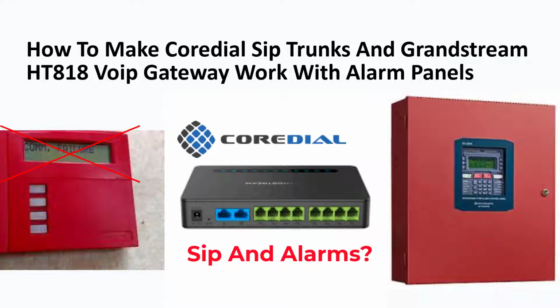However, with POTS lines being faded out these days, you want to have a dependable VoIP product that can communicate with a fire panel consistently, or you're going to need to pay the expensive cellular protocol cost to communicate with your panel. And after years of frustration trying to use VoIP lines with fire panels, I finally tweaked the Grandstream HT818 to communicate with the fire panels, enabling the completed proverbial handshake, or kiss-off, so to speak, and that's going to eliminate the comfail errors.